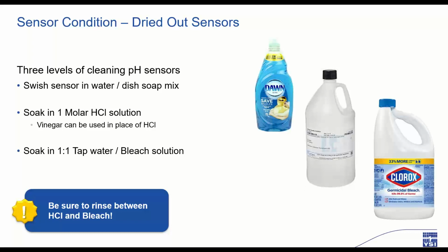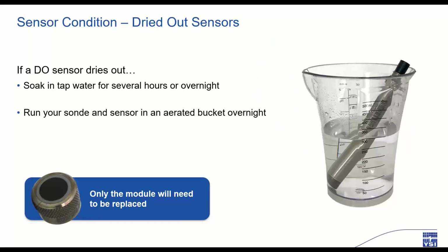And if you're doing both, the bleach and the HCl soak, make sure that you rinse very well between these 2 steps, as we do not want any mixing of the bleach and the HCl. And for those of you where HCl presents a problem for disposal, then just swap in vinegar in the place of the HCl.